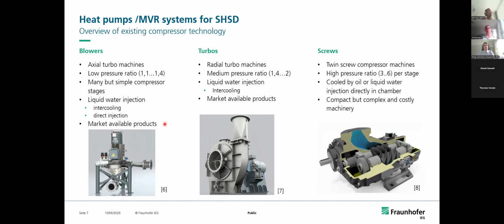Those are already market available products. Shifting to turbo machines, it's the same type of machine but with a different blade geometry — radial instead of axial blades — which increases the deliverable pressure ratio up to 2, meaning fewer stages are needed for the same pressure lift. They cost more, and also have intercooling but don't inject it directly after. They are also market available products.